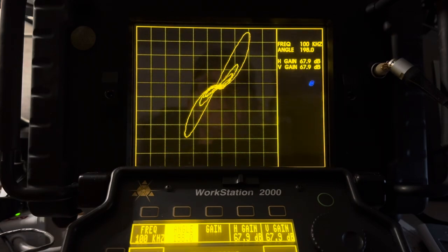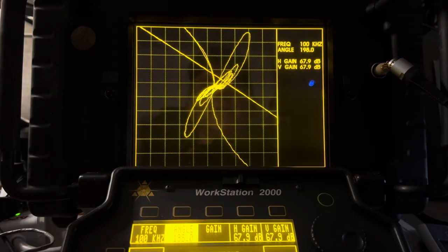See, another one - there's another through-wall hole. But the main thing I want you to note here is that the through-wall hole is set to almost 40 degrees, and the OD flaws have a lot of phase lag because they're far away from the inside bobbin probe coils.